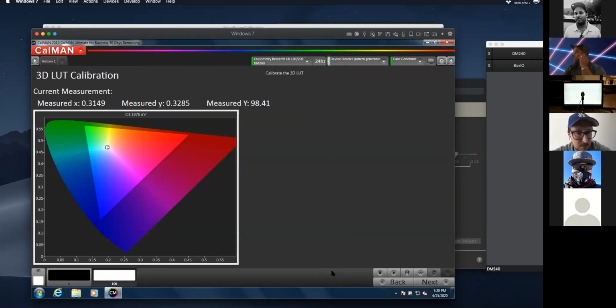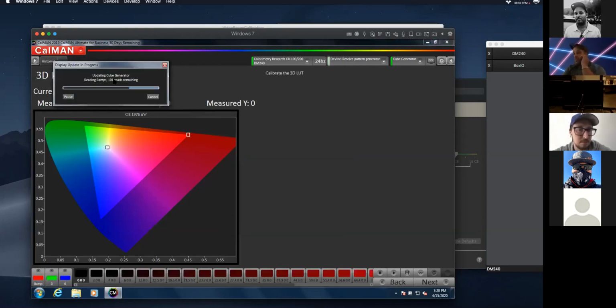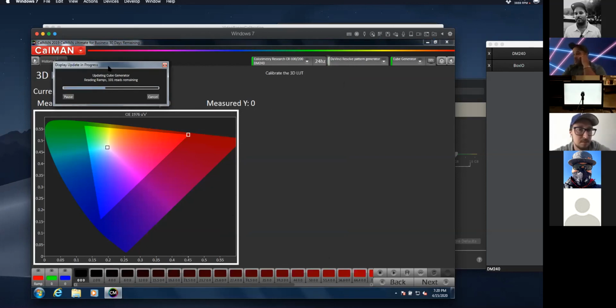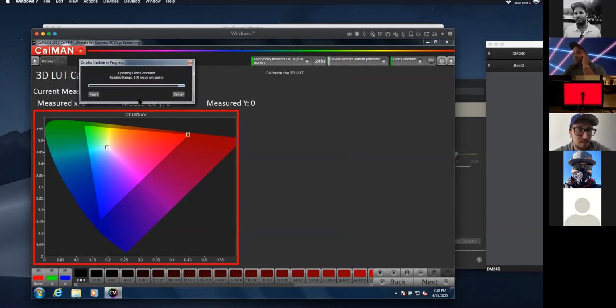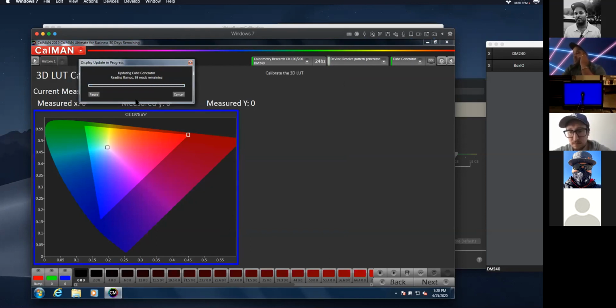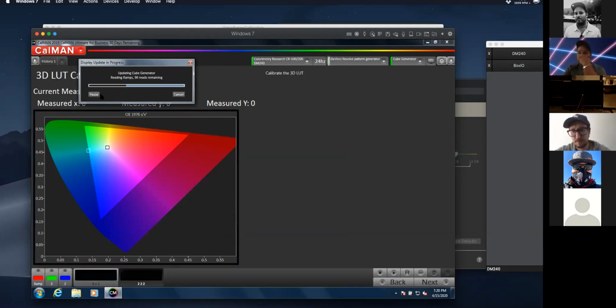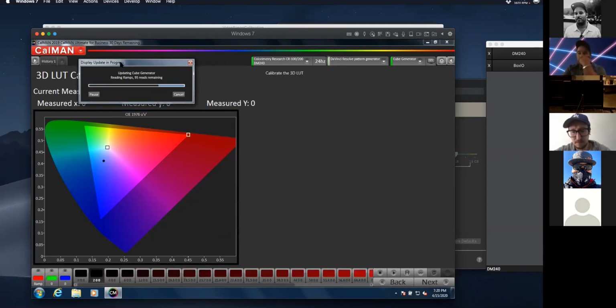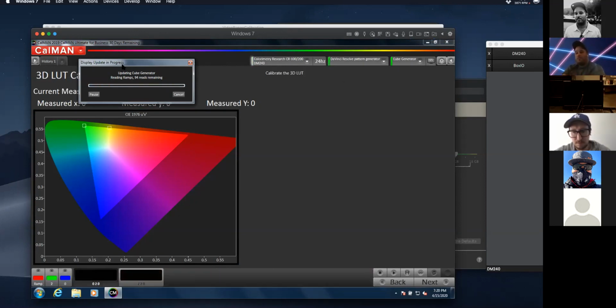I'm going to hit OK, and now it's going to start taking my readings. You'll see that it will give us a countdown timer here, telling us how many readings are remaining. And once that's done, it will automatically generate the LUT into the folder that we selected. Then we can drag and drop that onto the monitor, update the LUT, and do the validation. So once that's done, we'll show the validation. I know I rushed through some of that, but this will take a little bit of time as we're doing about 90 some odd more readings. So if anybody has any questions in the meantime, now would be a great time to ask them.